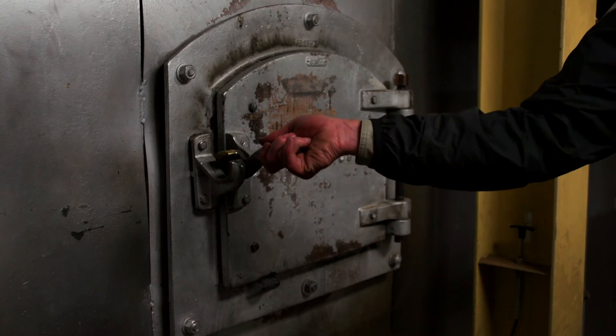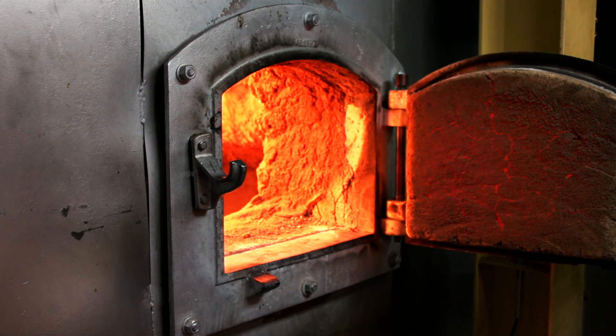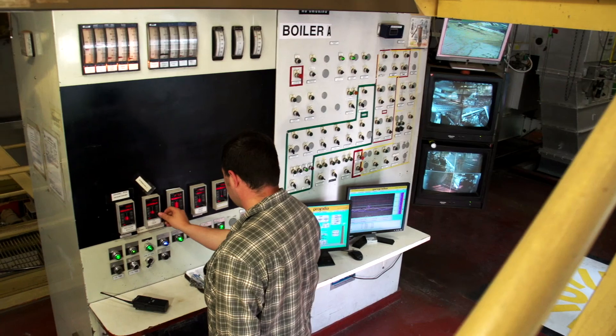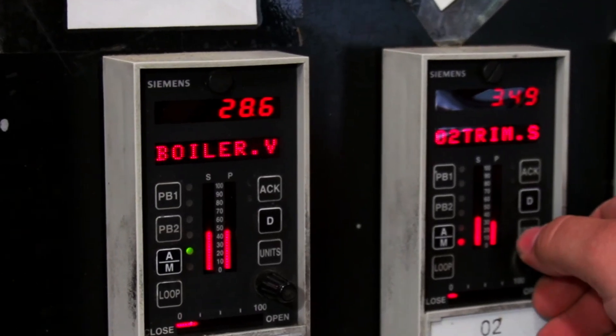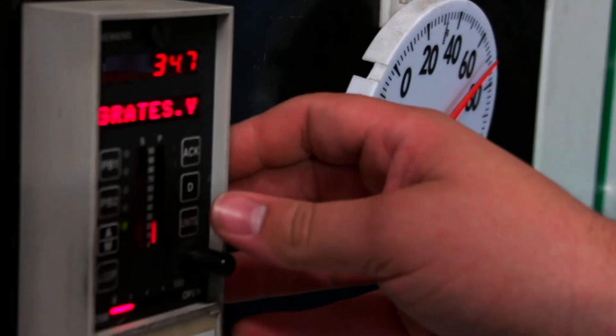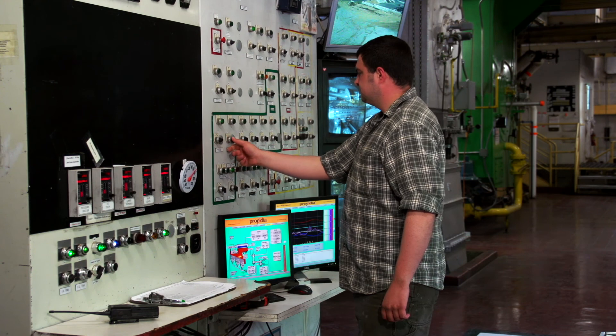When the wood is burned, the combustion gases reach temperatures as high as 3,000 degrees Fahrenheit. As these combustion gases flow through the boiler, the heat energy transfers to the water and converts it to steam. The firebox was designed to accommodate a wide range of fuel qualities. Moisture content is the biggest variable we have to adjust for — it can vary from more than 50% to less than 5%. Boiler operators are constantly adjusting the balance of air at seven places in the process to achieve the highest efficiency and cleanest emissions.